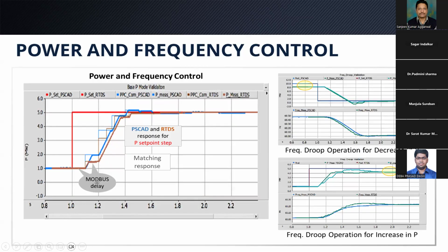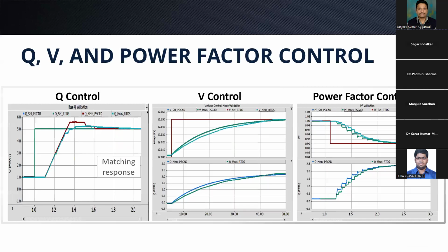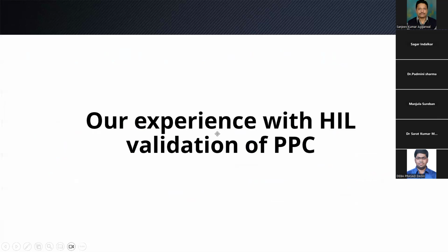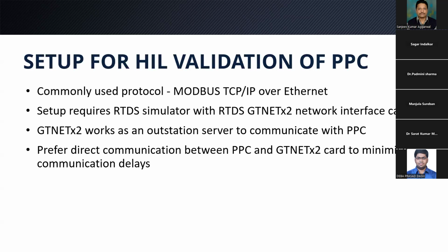Okay. Discretize the control and add the Modbus delay so that the model developed in PSCAD becomes a more real-world representation of the system. Right? Then you perform all the tests, and then we'll see whether the responses match each other or not. They may not match due to delays or certain time constants or physical differences between the model and the devices. Okay. We have performed this validation of PPC for multiple OEMs. We'll just briefly discuss that experience.